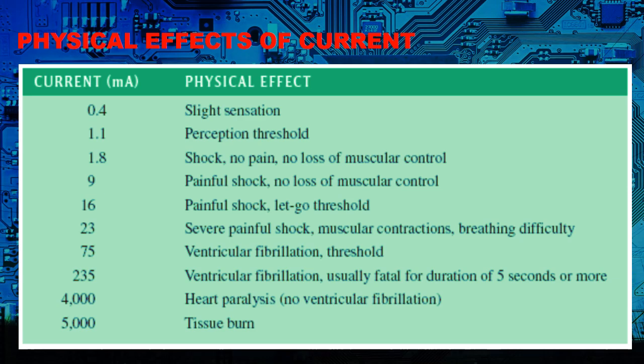the effect is a slight sensation, just some small effect. At 1.1 milliamps, we have the perception threshold, meaning a slight intensity of current. At 1.8 milliamps, we experience shock with no pain and no loss of muscular control. At 9 milliamps, painful shock with no loss of muscular control. At 16 milliamps, painful shock, and this is where we exceed the threshold of let-go intensity. At 23 milliamps, we experience severe painful shock, muscular contraction, and breathing difficulty.